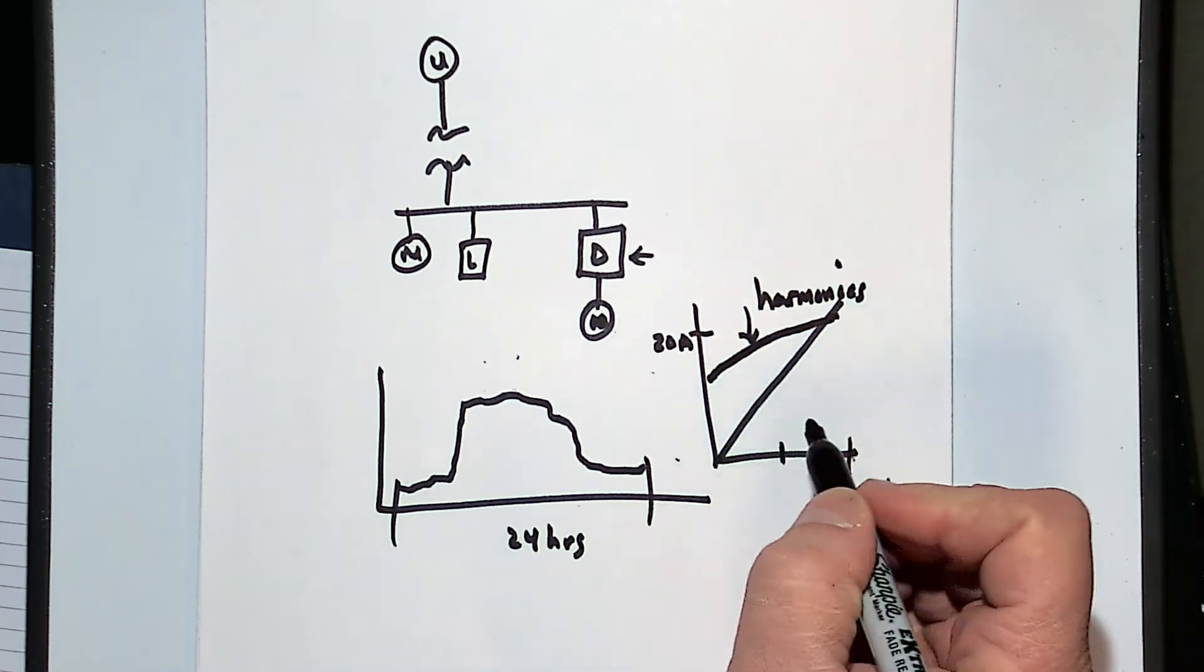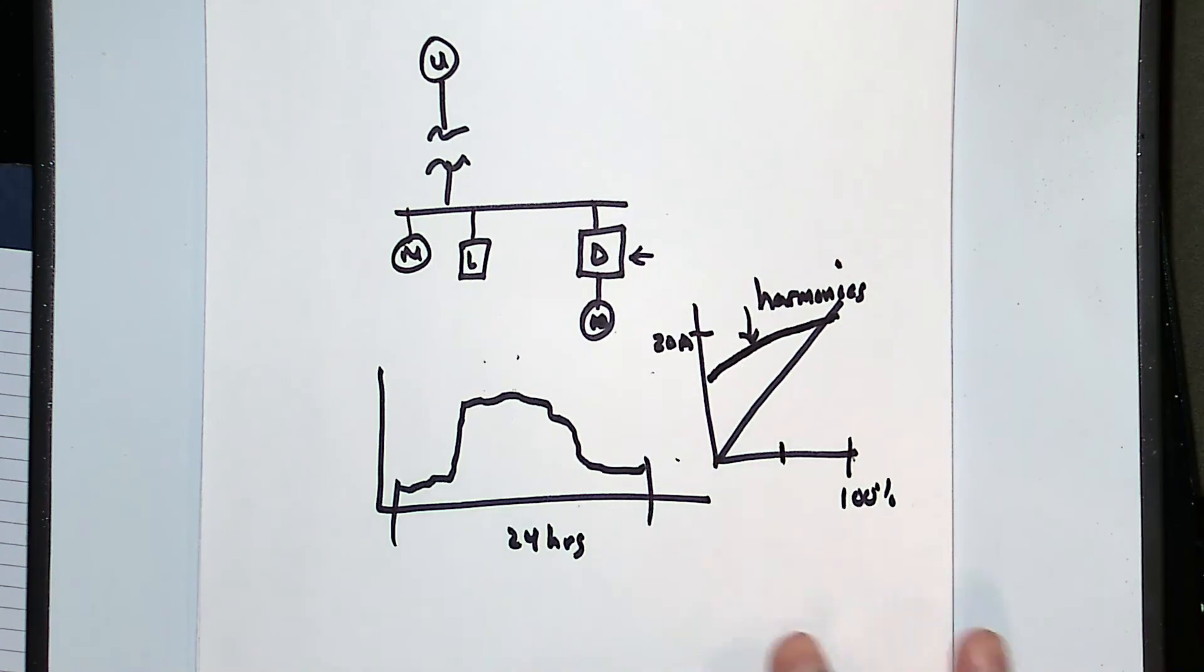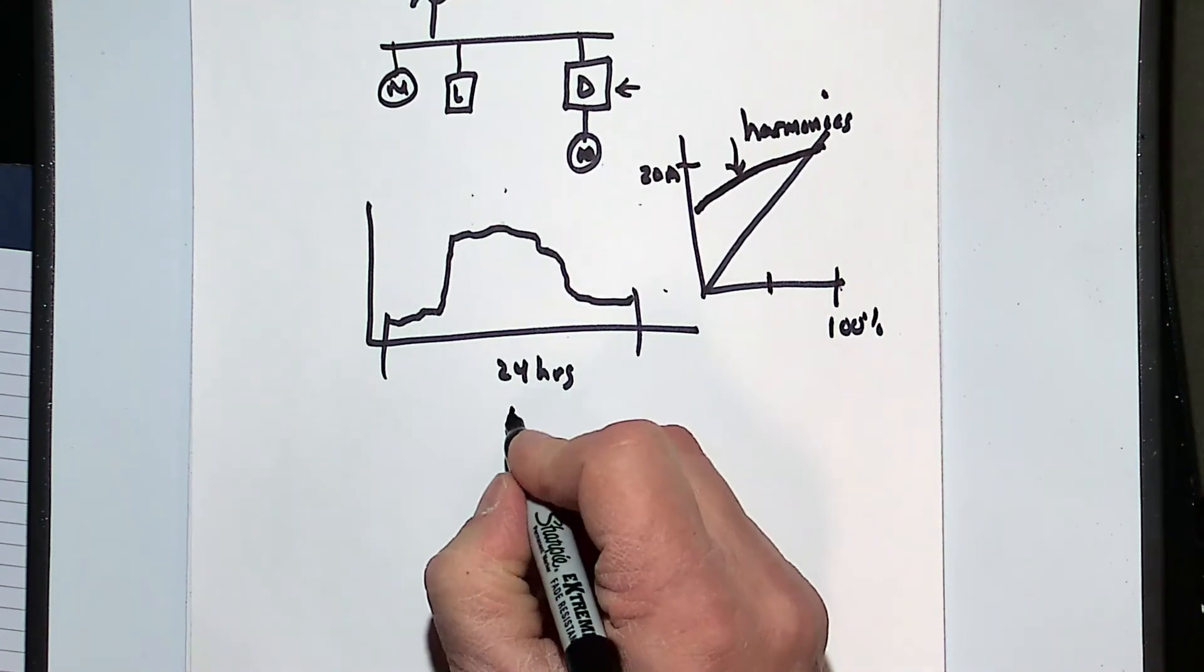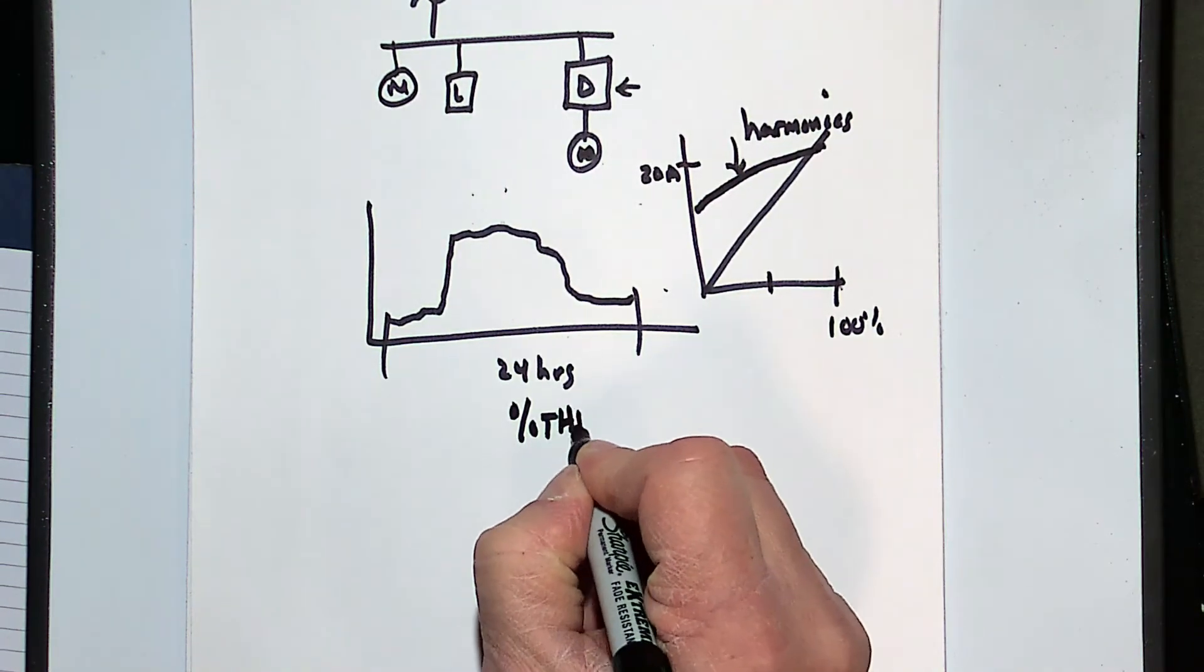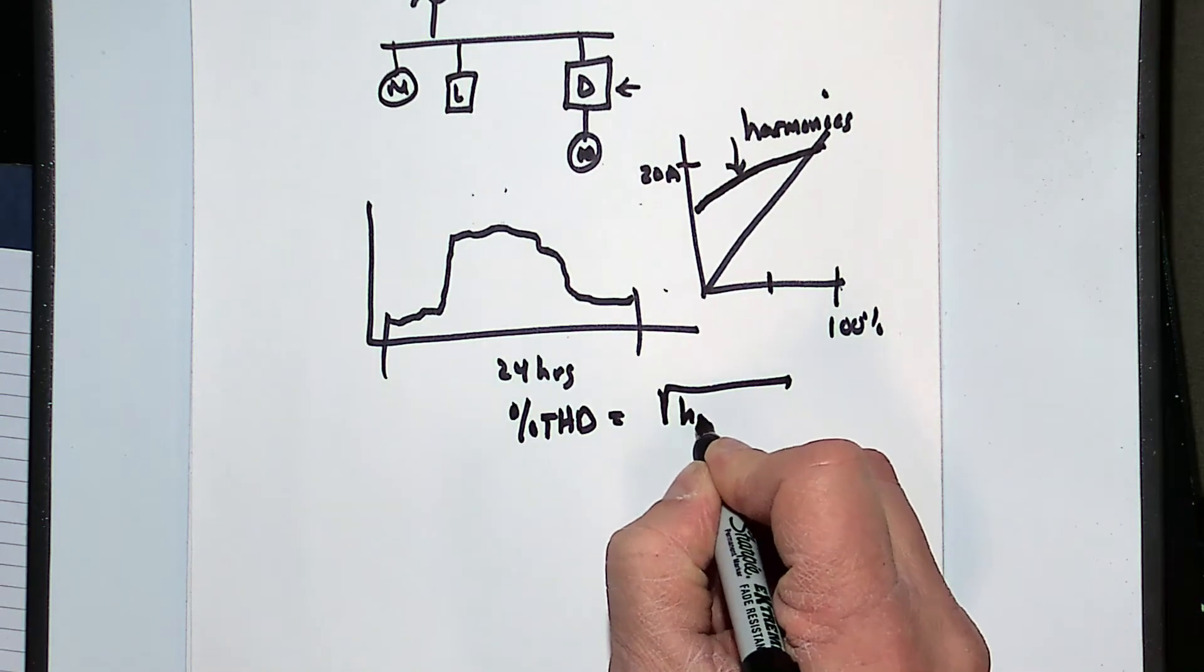And so what happens is at a very light load, my harmonics are very high. And so again, comparing that proportionally to the 60 hertz, because our percent THD is based on the square root of the sum of the squares of all the harmonics...